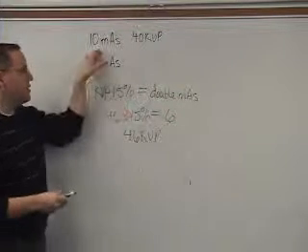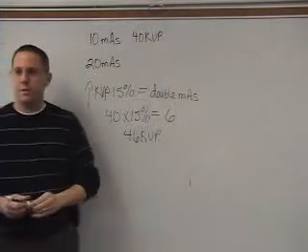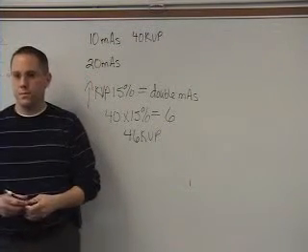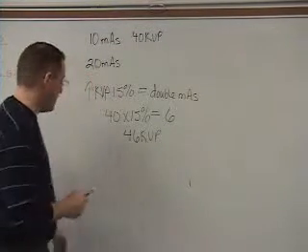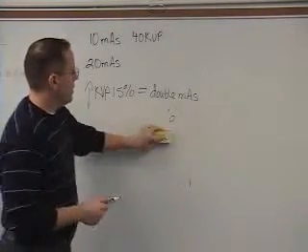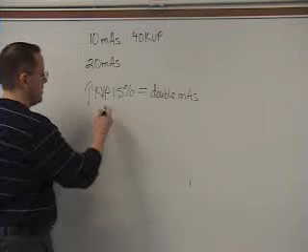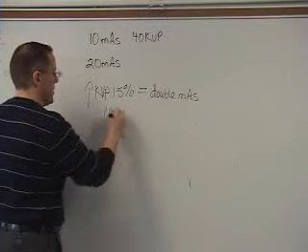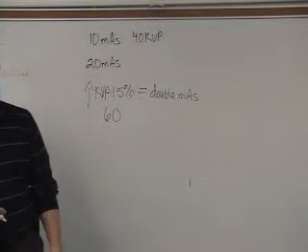We didn't have to change the amount of radiation that we exposed them to. So let's do another one. Let's say that your kVp is 60, and we want to increase it 15%.